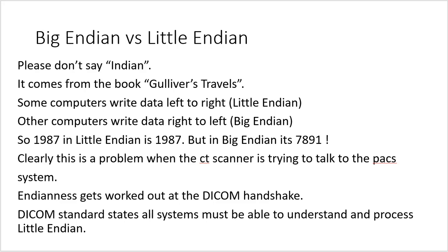And clearly this is a problem if the CT scanner is trying to talk to the PACS system. They need to be speaking the same version of Endian. So Endianness gets worked out at the DICOM handshake. When they first make a connection, one of the first things they start to figure out is, hey, what version of Endianness are we going to use for this communication? The DICOM standard states that all systems must be able to understand and process Little Endian. So Little Endian is the go-to for two DICOM things speaking to each other.